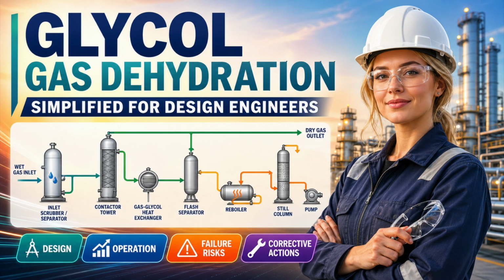Instrumentation must also protect the process, not merely display it. Pressure, temperature, level, and differential pressure should support operation, while high-temperature shutdown, flame failure protection, low-level protection, and other safeguards should address credible rapid failures. A gauge is information. A trip is protection. Do not confuse the two.